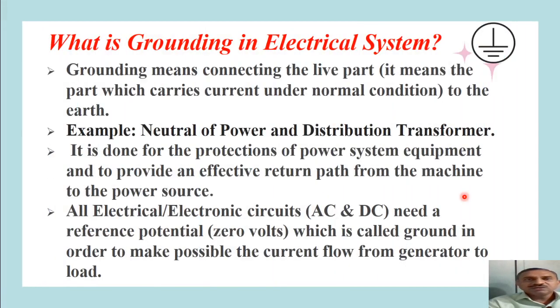Now let us see what is grounding in electrical system. Here we are describing grounding by considering the Indian scenario. So grounding means connecting the live part of equipment to the earth. The live part is going to carry the current under its normal working condition. The best example of grounding is the connection of the neutral of power and distribution transformer to the earth. Now this is again to be done by the earth electrode, which will have a direct contact with the earth.